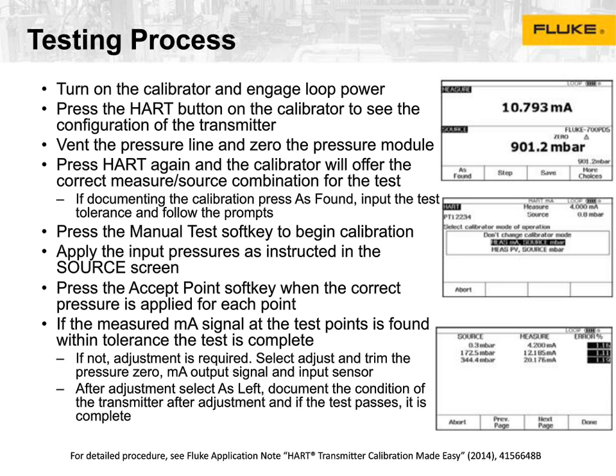Pretty straightforward. If you have errors, at that point you need to do adjustments. I'm not going to talk a lot. I've got an example of 3 here that are out of tolerance, and so you see they're all highlighted. All 3 points are highlighted here. And you can actually go back, do the adjustment on the trims, whether it be on the input or the output side, and be done. Again, we have a detailed application note that we've just revised, so this has the latest and greatest information that you can get far more detail on. Since I'm running out of time, I'm going to skip this.